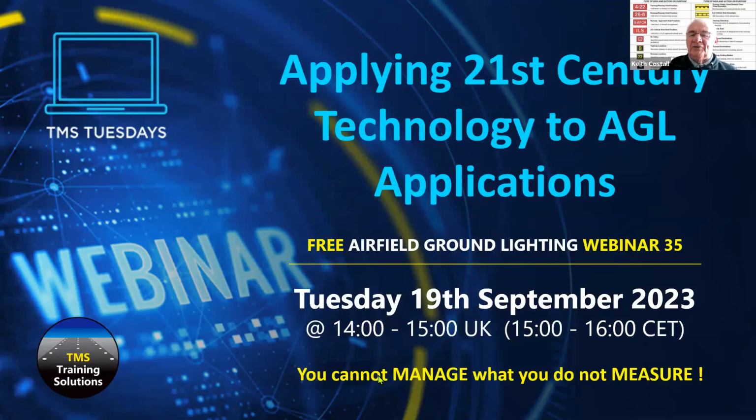Mind you, we soon removed that leaflet, of course. But when new technologies are introduced by the technologists, this is the answer to the world. But the reality is, let's take LEDs, an LED will last many, many hours. They do deteriorate faster than was first thought, but it's the electronics, the driver associated with that LED, where main failure comes in, be it condensation inside the lighting fixture, be it heat, be it whatever the reasons behind it. It's the electronics rather than the actual LED itself, which is a light emitting diode.